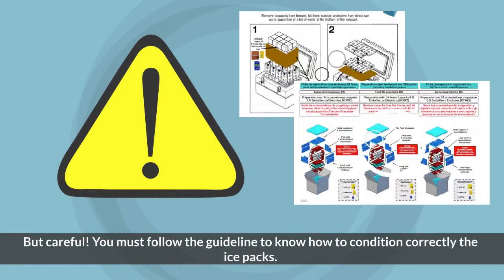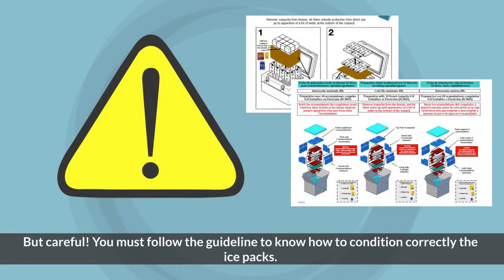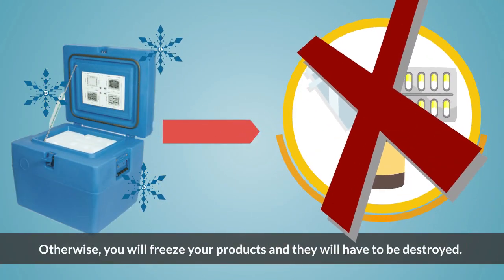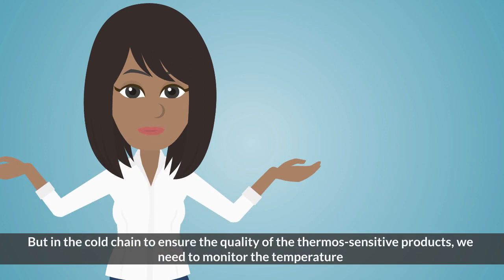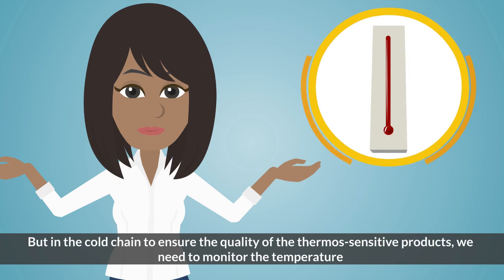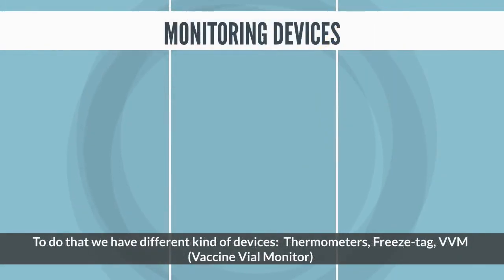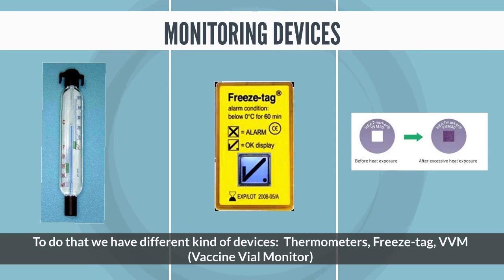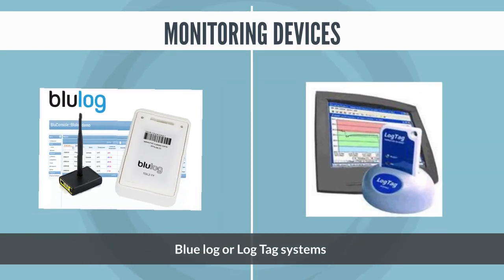But be careful — you must follow the guidelines to know how to condition the ice packs correctly. Otherwise, you will freeze your products and they will have to be destroyed. To ensure the quality of thermosensitive products, we need to monitor the temperature. To do that, we have different kinds of devices: thermometers, freeze tags, VVM (vaccine vial monitor), blulog, or log tag systems.